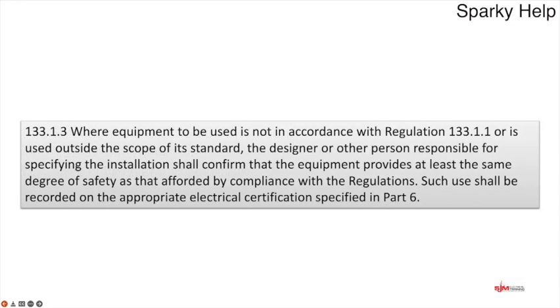The next regulation it referred to, it says 133.1.3, it says where equipment to be used is not in accordance with regulation 133.1.1, or it is used outside the scope of the standard, the designer or other person responsible for specifying the installation shall confirm that the equipment provides at least a degree of protection. So like I say, whatever you put in has got to be equal to or above whatever the rest of the regs that you've deviated from says. For example, and this is only an example, if it said a particular enclosure had to be IP2X and you decided to go, no, I'm going to put some weird thing in, it's got to be at least IP2X that you put in. If it doesn't specify on it, you'd have to make sure that it does, check that, which is basically a little finger ultimately.